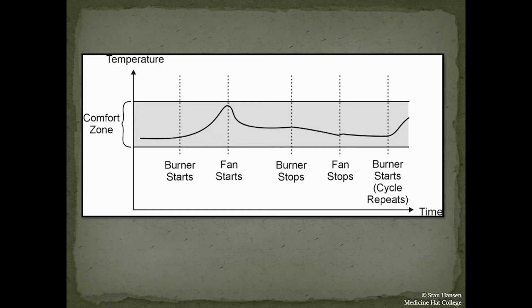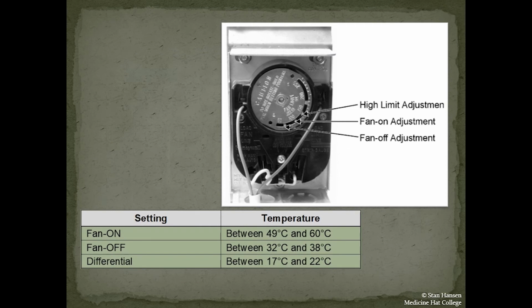In the case of economy, we want to make sure that the fan off is not set too high because this can waste heat, which means the heat can escape through the chimney instead of being used inside the house. Typically for my fan controls, I want the fan to turn on anywhere between 49 and 60 degrees Celsius, and I want my fan to turn off anywhere between 32 and 38 degrees Celsius. The difference I should see between these two settings should be between 17 and 22 degrees. If they are too close, it's going to create cycling. Keep in mind, a lot of these settings are going to be site specific, so we can adjust them at the site itself.